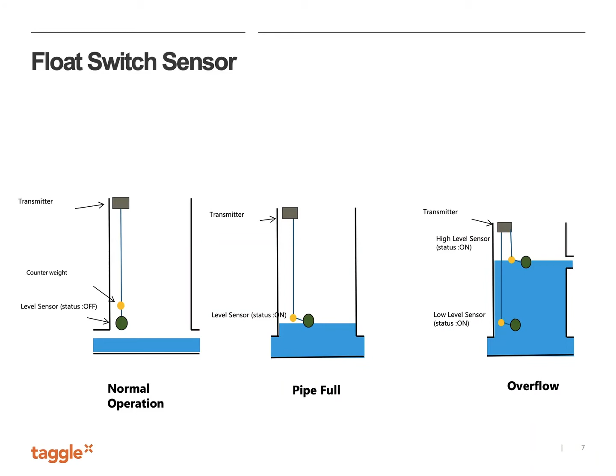Taggle worked on a new generation of transmitter based on that feedback, so that there's some business logic in the transmitter to be able to distinguish between a rise or a fall in the float switch and just the bouncing around of the ball from turbulence. Overall, this is a pretty good mechanism for monitoring sewer levels. But where it becomes a little bit more interesting is when you get to correlate the behavior of the sewer levels with what's going on elsewhere.